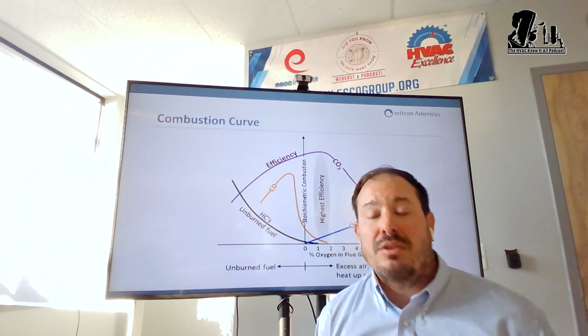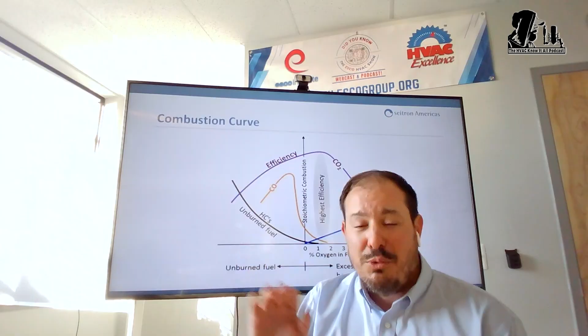So, that's another. What are you talking about? System 636 that's specifically designed for venting of high efficiency appliances? Or are you talking about? No, I'm talking about standard Schedule 40 PVC piping that I see on a daily basis. Okay. That is not meant for what it's being used for. We could do a whole podcast on venting materials if we wanted to, but going back to that acidity and the NOx and the byproducts, it's not made to withstand that kind of stuff over time.